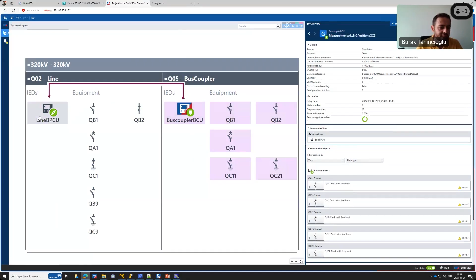And I expect that this line bay protection controller would also subscribe to these positions. I can simply make a small check. I can now trigger any positions, like I can close this and see the interlocking sign. What's the interlocking sign? That's the SCILO. So the line bay protection controller is evaluating this information that it receives from a simulated IED in its logic, receives this value, and also changes its SCILO, the control interlocking logic node, to false, because you cannot close it. So if you try, you cannot close it.